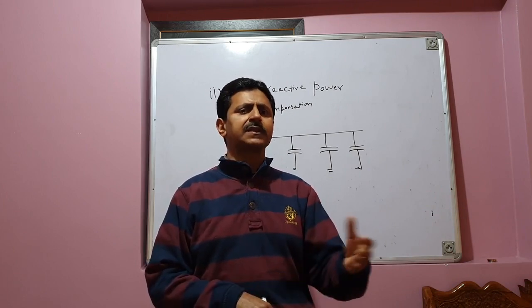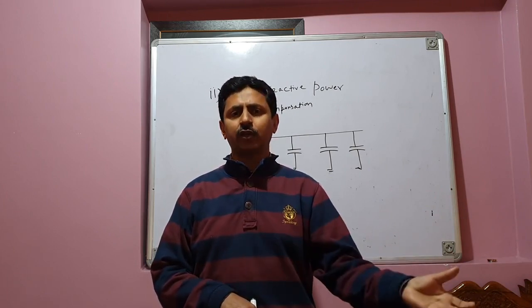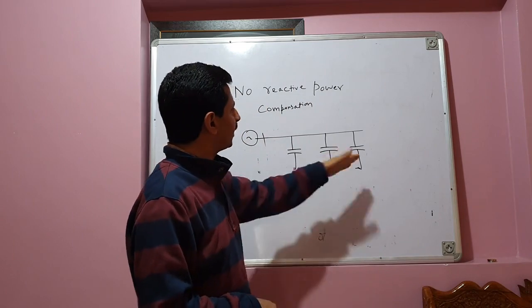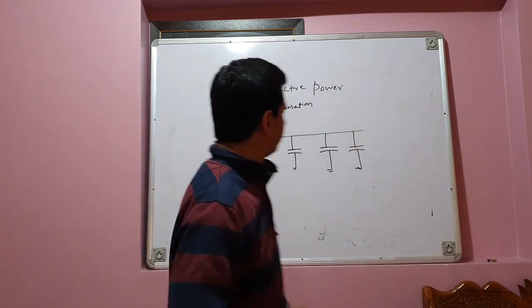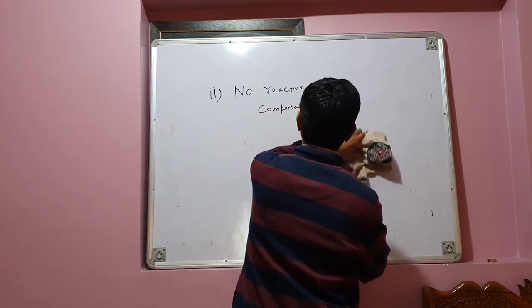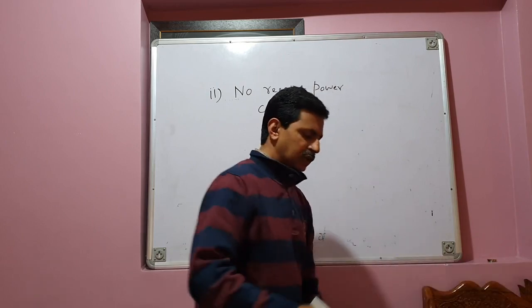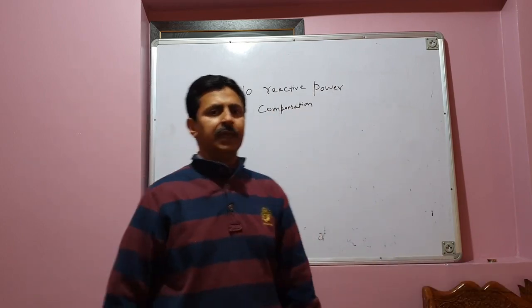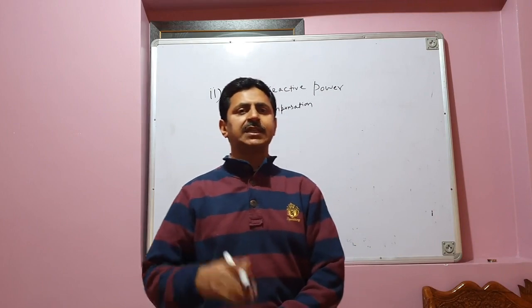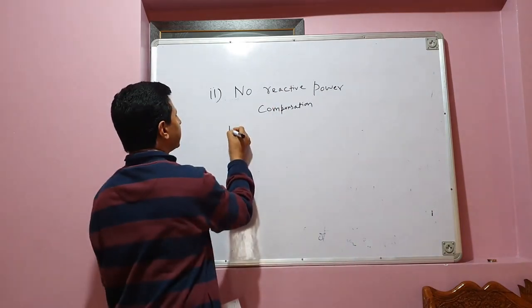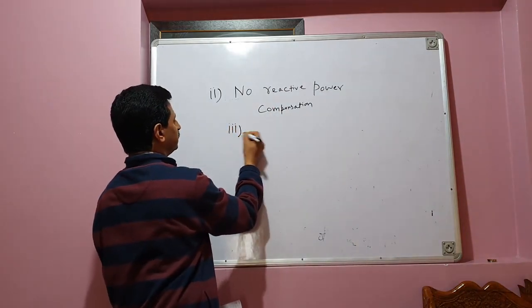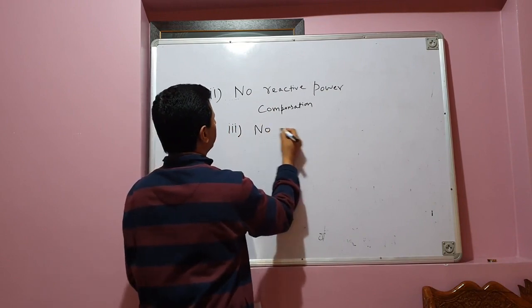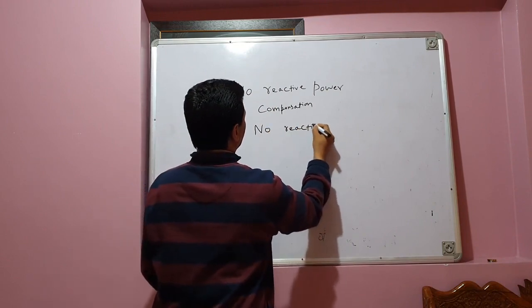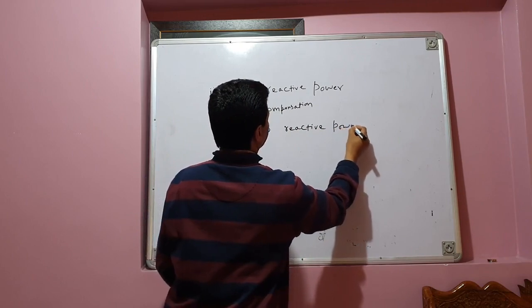Because in DC there is no reactive power, right? So therefore this reactive power compensation is not required if you are transmitting DC power, and you are not transmitting power over AC lines, you are transmitting power over DC lines. So this is the second advantage offered by HVDC power transmission over AC power transmission. What is the third advantage? No reactive power loss.